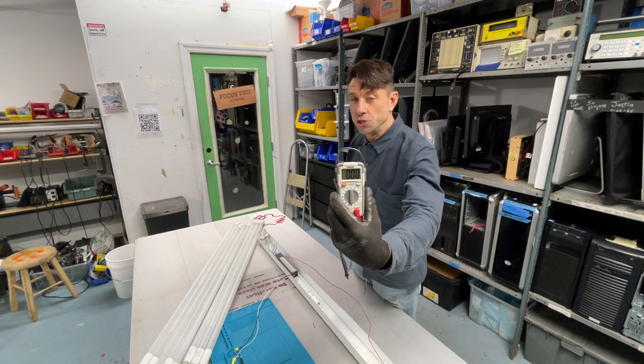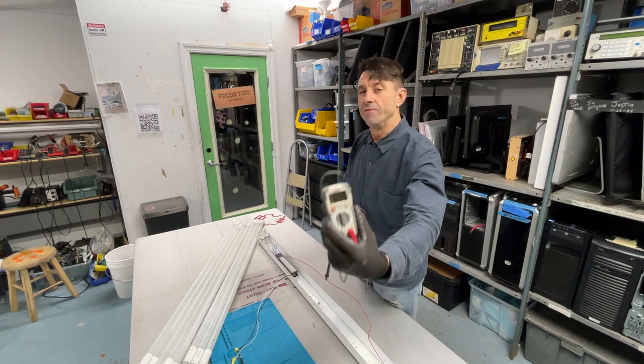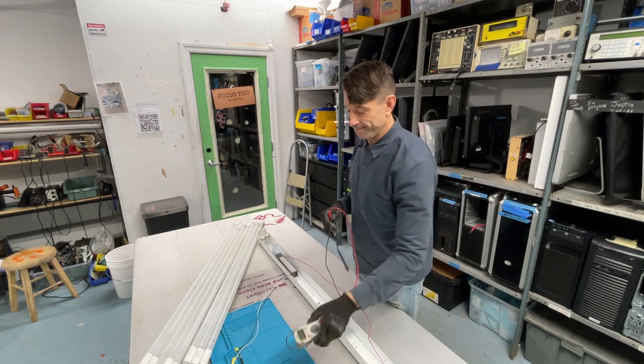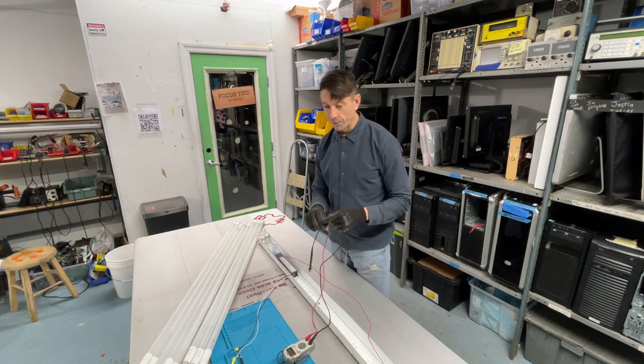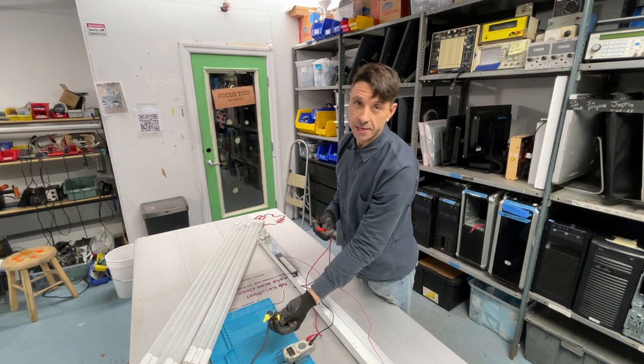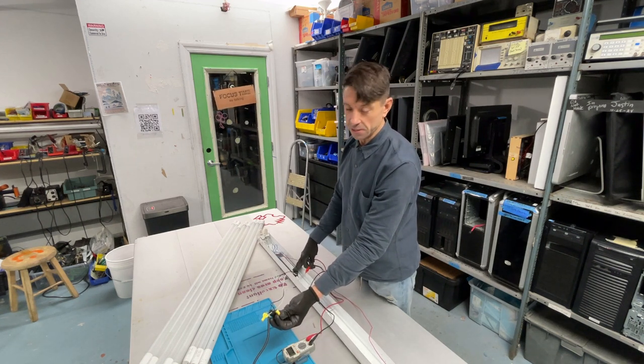This is how we're going to start. It should show zero on your meter. You can see here I have it on 500V. First we'll simply start by connecting the power to the ballast itself.